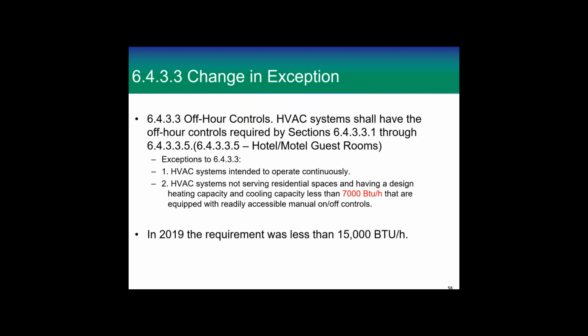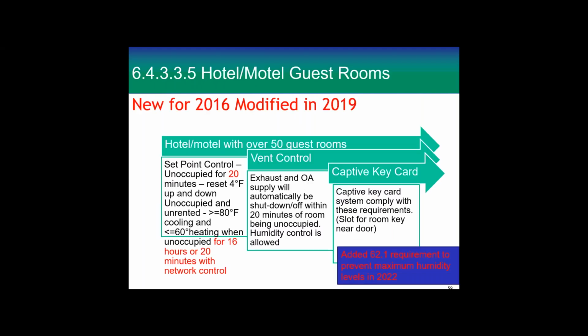So the exceptions are when they're intended to operate continuously, and HVAC systems not serving residential spaces and having design heating capacity and cooling capacity less than 7,000 BTUs. That is the change for 2022. In 2019, that number was 15,000. So we've cut that in half for these. We've really increased the amount that do not qualify for the exemption.